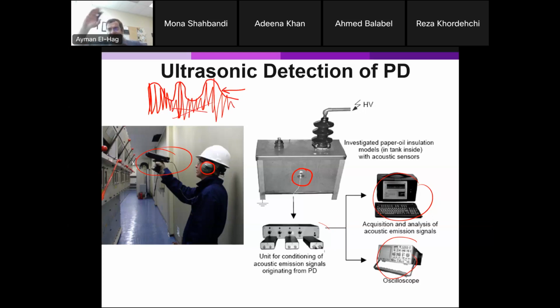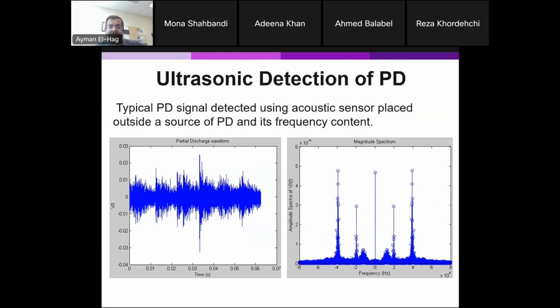So by just having the envelope of the ultrasonic signal, with the processing happening inside the device, you can listen and hear something coming out of this. This is why we use those headphones. This is a typical partial discharge signal coming from a transformer structure, using the piezoelectric sensor. This is something that we measured sometimes, and you can see the frequency content is basically in kilohertz, like 20 kilohertz, 40 kilohertz. So it is very small compared to the RF antenna.